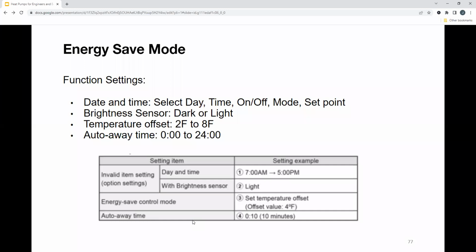So if you do have an occupancy sensor in your space, whether it be third party or a manufacturer's occupancy sensor, this will go into a 4-degree temperature setback after 10 minutes of not seeing anyone in the space. These offsets can be set between 2 Fahrenheit and about 8 Fahrenheit overall. And then you can readjust your auto away runtime as much as possible. If I did set this up in an office space, it goes on at 5 p.m., and at 6 p.m. I'm still working, adjusting the temperature, and the occupancy sensor sees me. If I do leave at 8 o'clock, this will adjust to the temperature set offset.